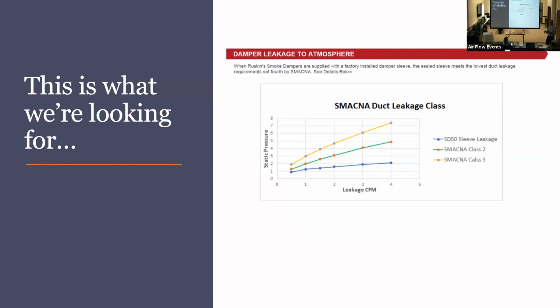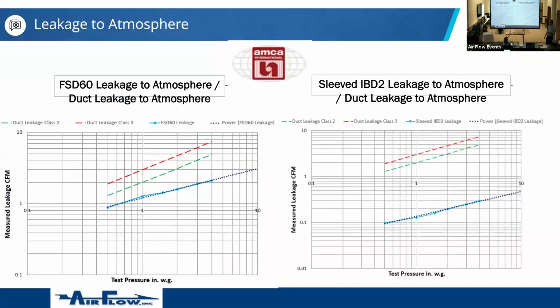So what does that mean? If you're doing field testing, you can test way more duct and go right through the damper. So that's a huge benefit to the contractor. Do contractors know this and say, ooh, I want to get Ruskin life safety dampers because the sleeves don't leak? No, they don't. Probably because they're probably not testing that much, but the problem is solved. Okay, so this is fire smoke damper leakage. Here's the damper, here's class 2, here's class 3, here's a fire damper, here's class 2. So you can get over the life safety thing if you use Ruskin. I don't know if other guys have tight sleeves, but you can solve a lot of testing issues with just this little bit and a little bit of information.